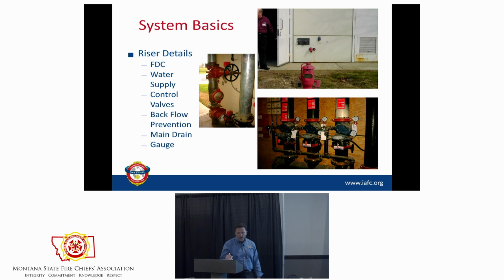Main system control valves right here on this thing. In a very small riser assembly, a single riser, this might be the only control valve you get. So remember we said keep it small? There may only be one riser in a building, so you're only going to close that. Fire department connection, what's this thing right here? What? Say it loud and proud.